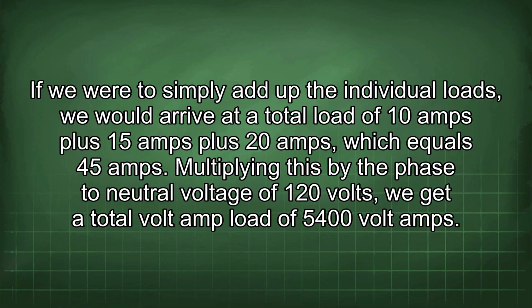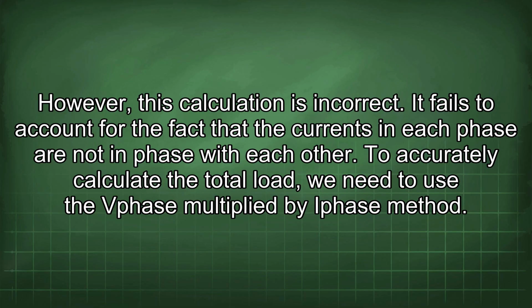If we were to simply add up the individual loads, we would arrive at a total load of 10 amps plus 15 amps plus 20 amps, which equals 45 amps. Multiplying this by the phase to neutral voltage of 120 volts, we get a total volt-amp load of 5,400 volt-amps. However, this calculation is incorrect. It fails to account for the fact that the currents in each phase are not in phase with each other. To accurately calculate the total load, we need to use the Vphase multiplied by Iphase method.